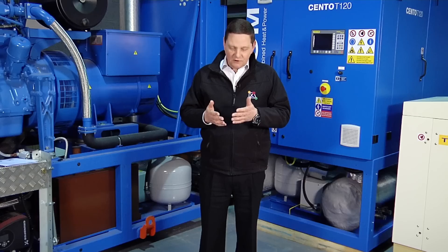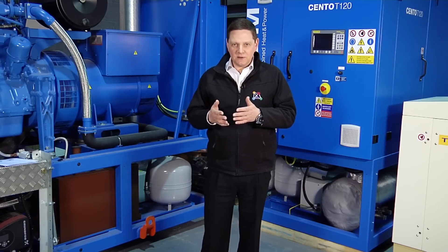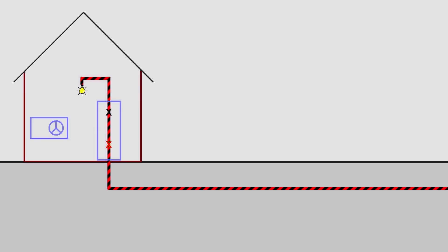You may not understand those terms so I'll briefly describe what they are. Running in parallel with the mains simply means that electricity coming into your building from the transformers out in the street — the public power supply — and electricity coming into your building from your generator or CHP, combined heat and power unit. This electricity comes in, the frequency and the voltage are exactly the same, so the electrical loads within the building have no idea they're being fed from two separate power supplies. These power supplies are synchronised so they're running together.